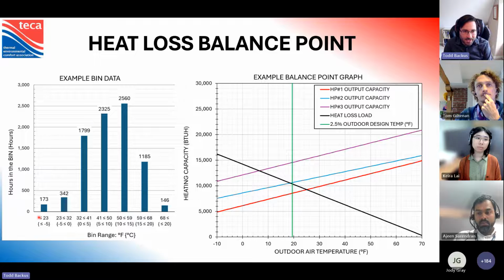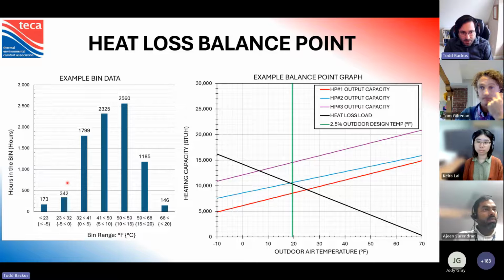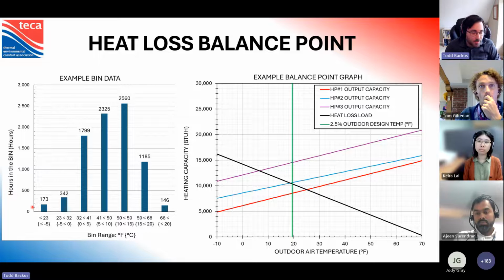And that's kind of what I was trying to highlight with this bin. Even though you might be serving this by code, there are going to be some hours that are actually below the code requirements. So you have to ask yourself as a designer, what is my client's tolerance for having that indoor set point temperature drop? I work a lot in really high-end residential. And so for me, the answer is they do not have a lot of tolerance for not being able to meet even the most extreme temperatures, which is why I tend to design further away from this code minimum.